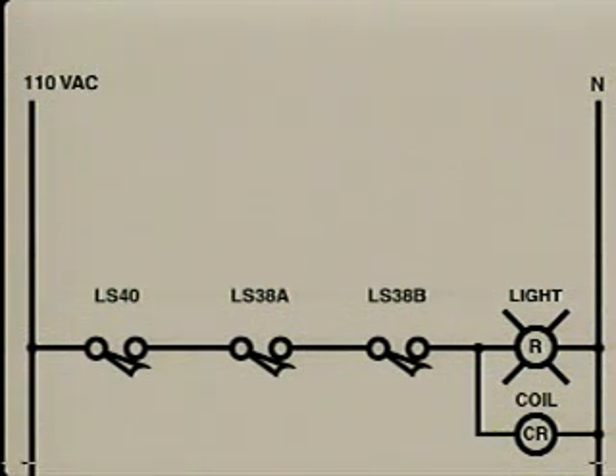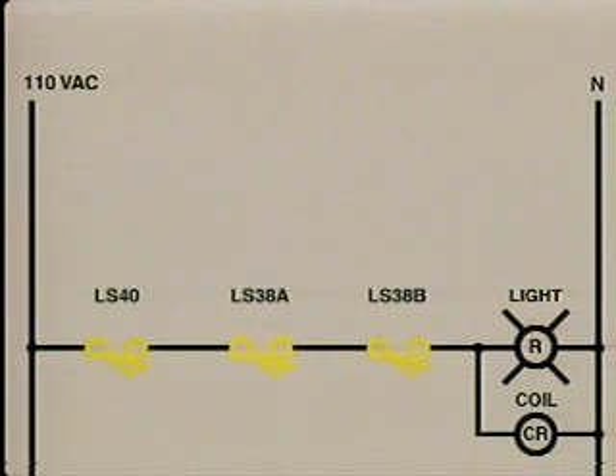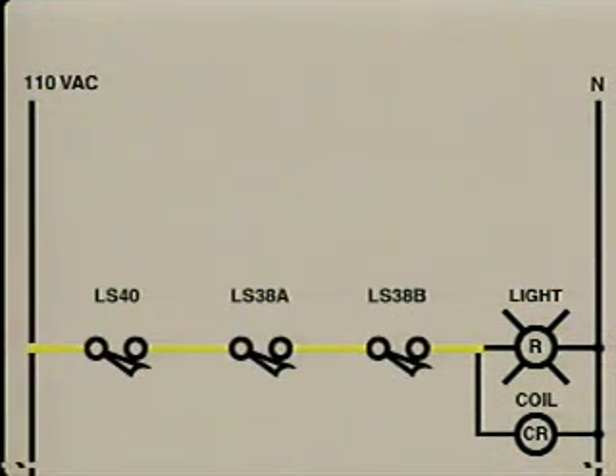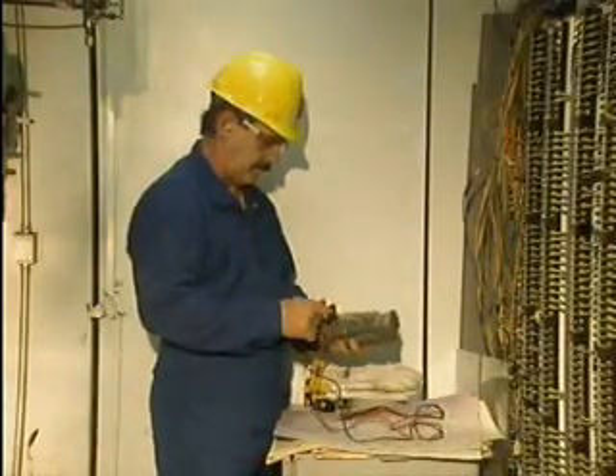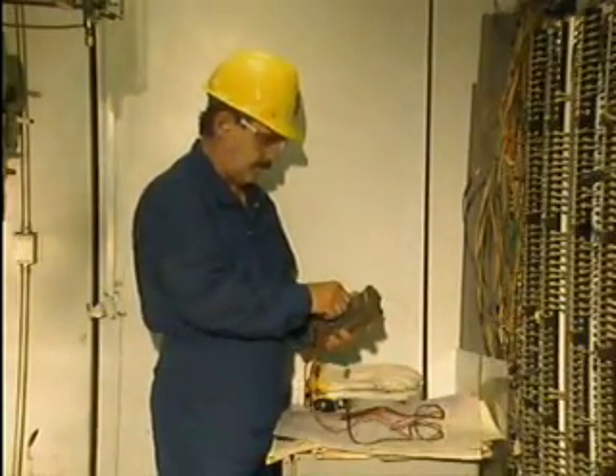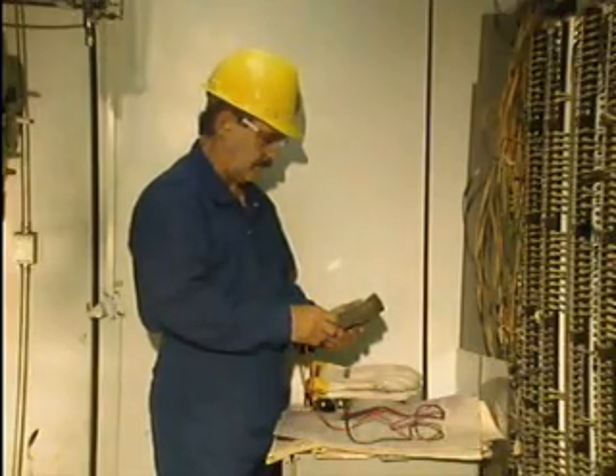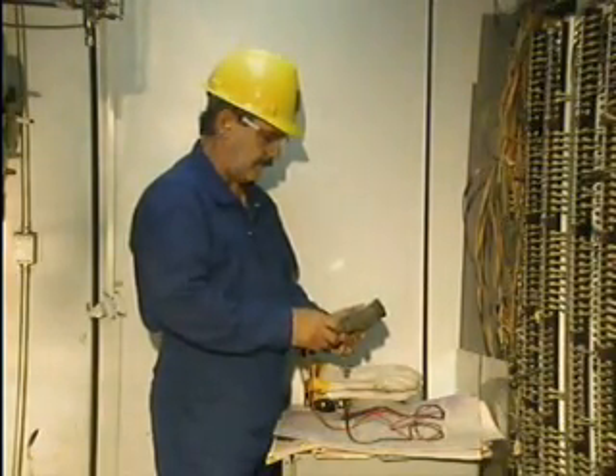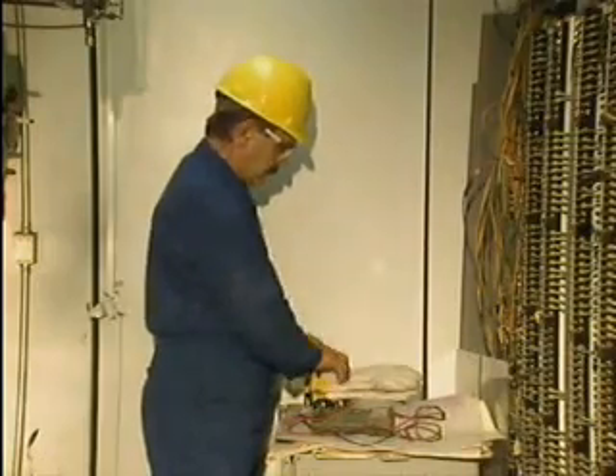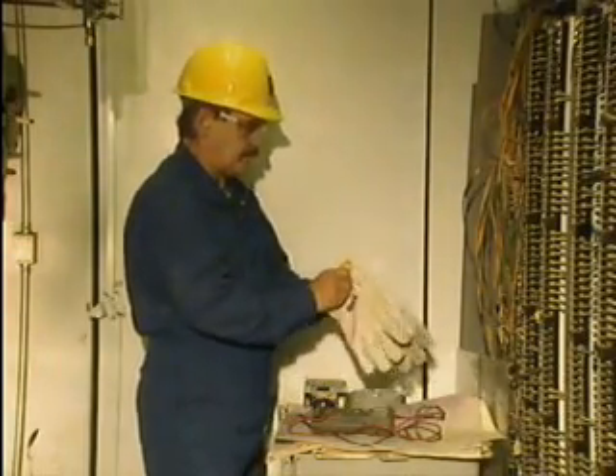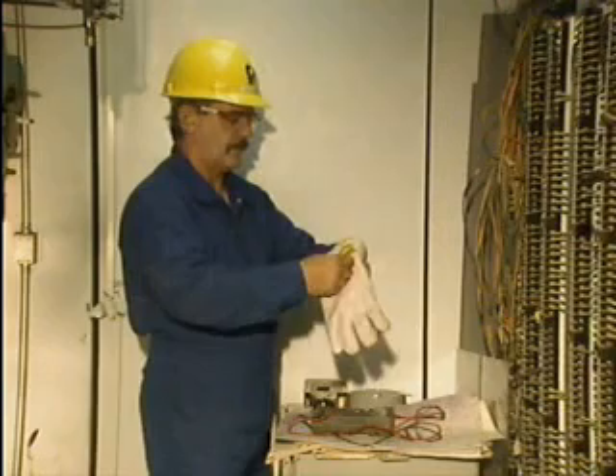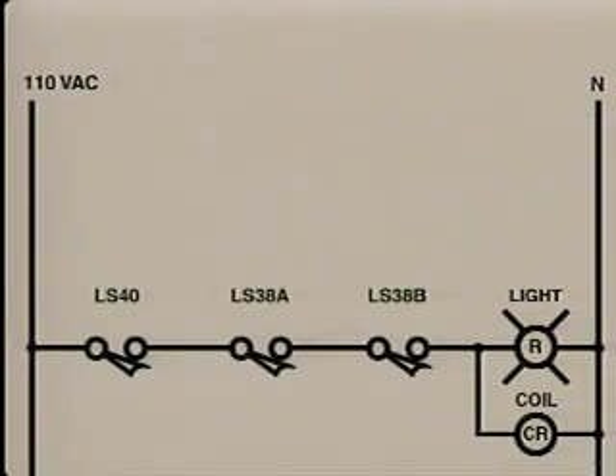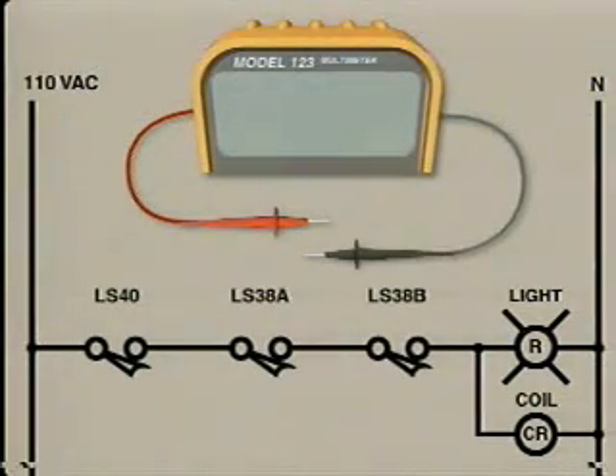Since both the indicator light and the relay's coil require that all 3 limit switches be closed, the electrician decides to check the limit switches and the wiring that connects the limit switches to the light and the coil for an open. To do this, he goes to the wiring termination panel for the circuit and sets up his multimeter to measure voltage. Since he'll be working near exposed energized electrical equipment, he will use approved insulating gear to protect himself against electrical shock.